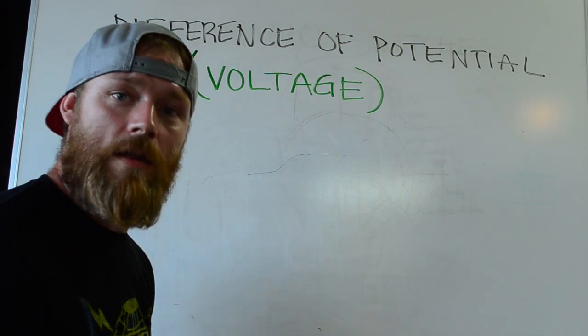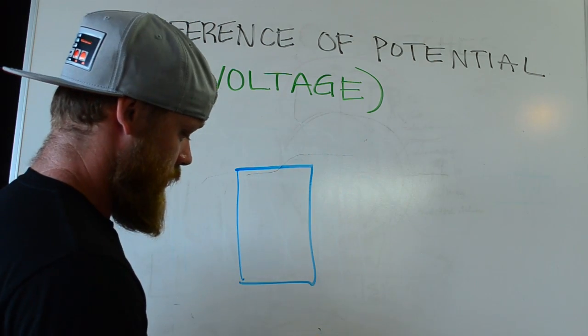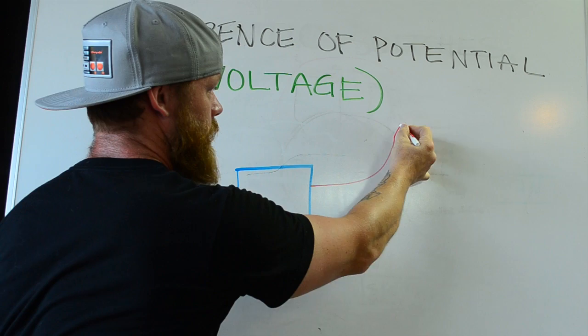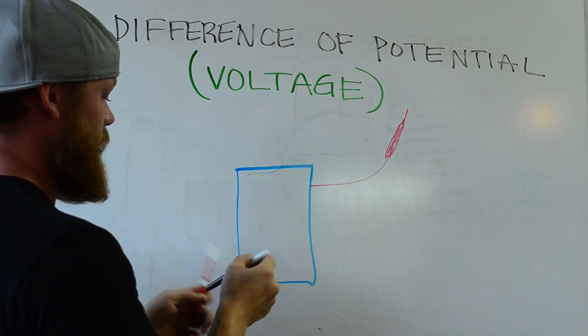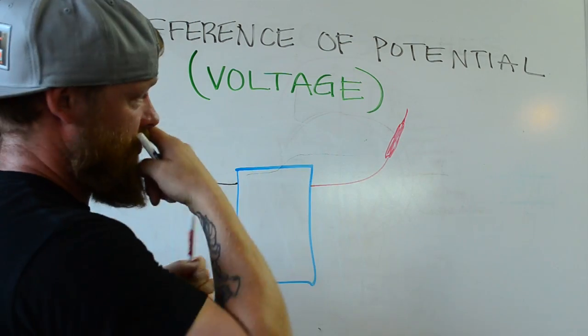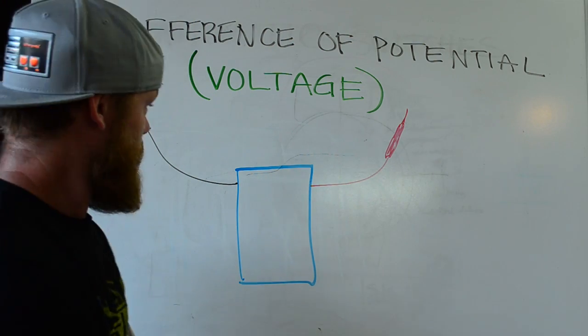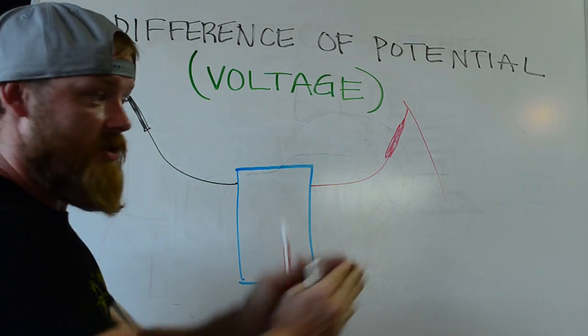Just understand that there are certain things in an electrical system that are at the same potential, and there are things that are at a different potential. So when you have a multimeter, you've got one red lead with a little spike on it and one black lead with a little spike on it. They do that because you're trying to find two different potentials — a positive and a negative, or a hot and a neutral, or a hot and another hot. So if you have one hot wire and another wire coming in, you're probably going to have 208 volts or 240 volts — such a difference of potential that the meter can read the strength of that difference.